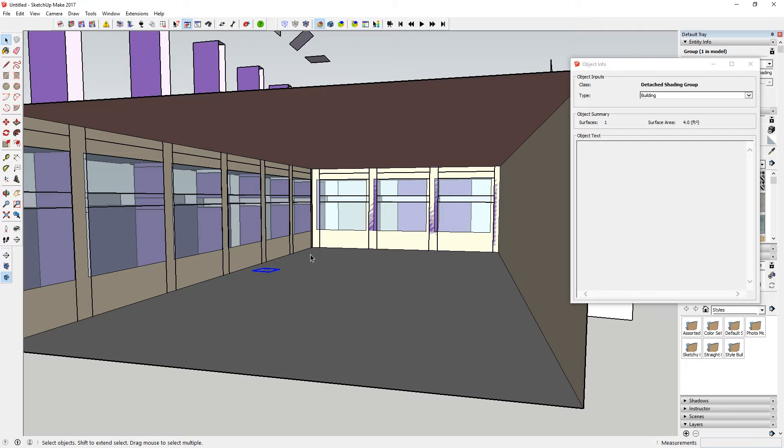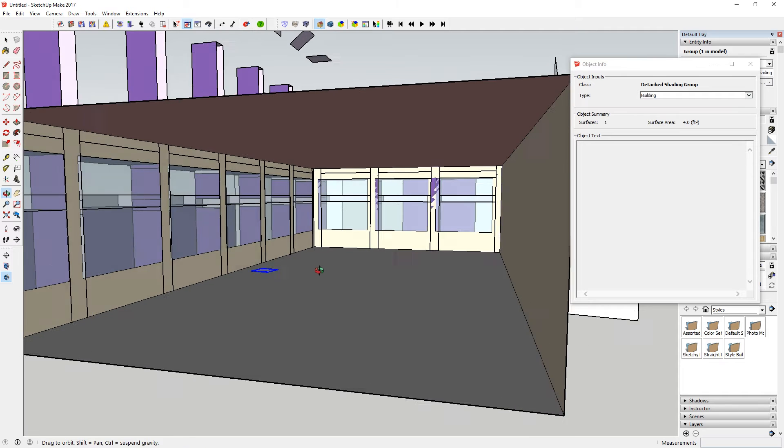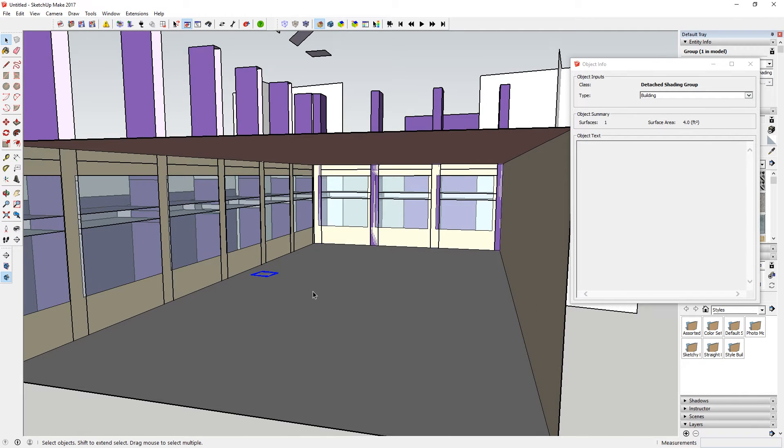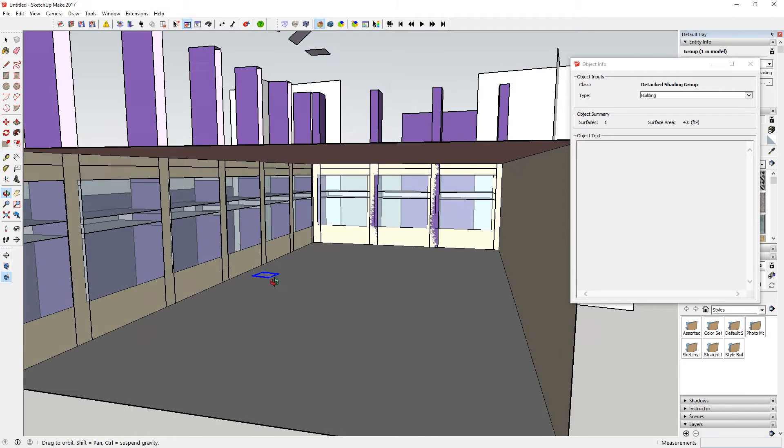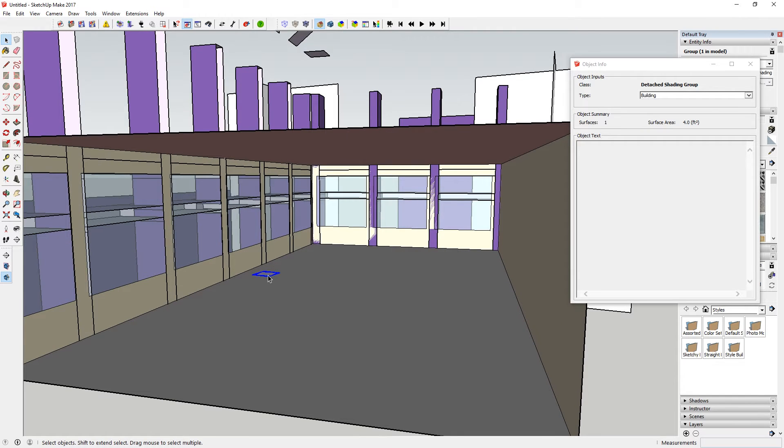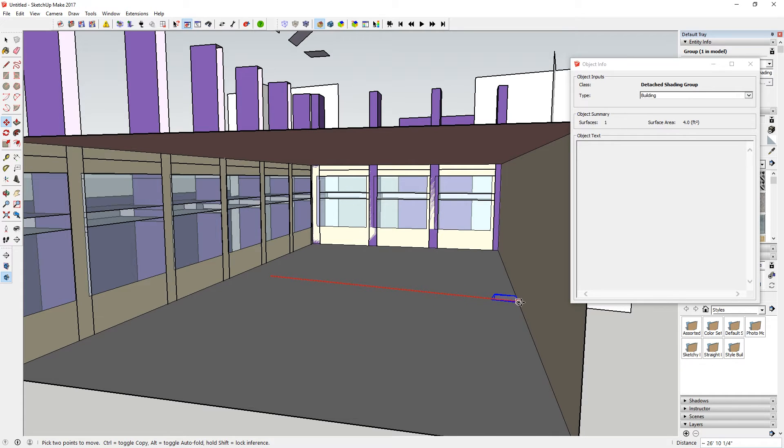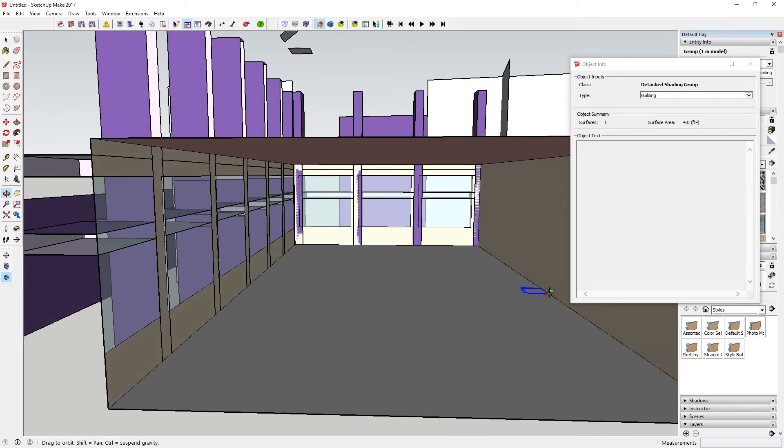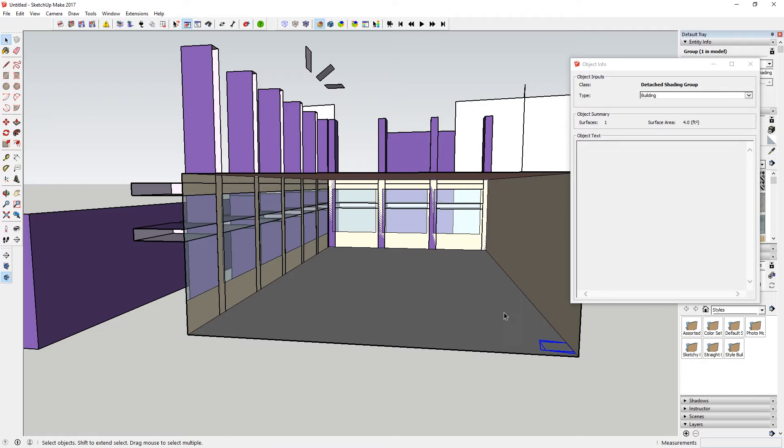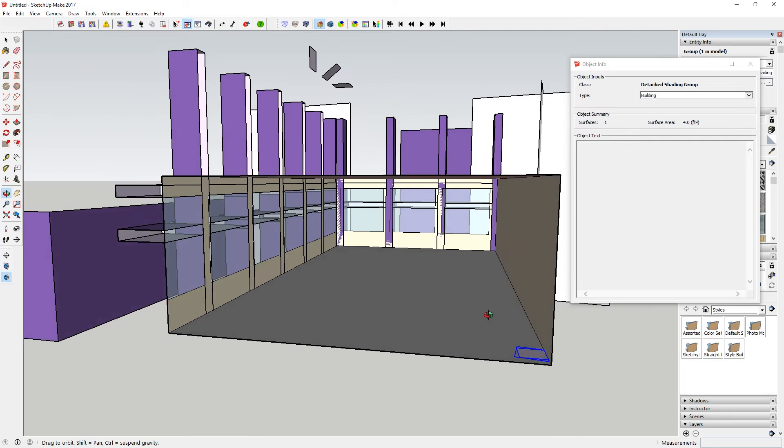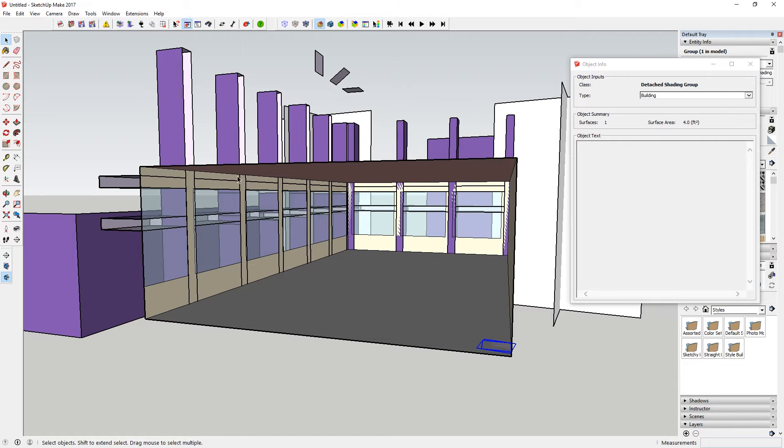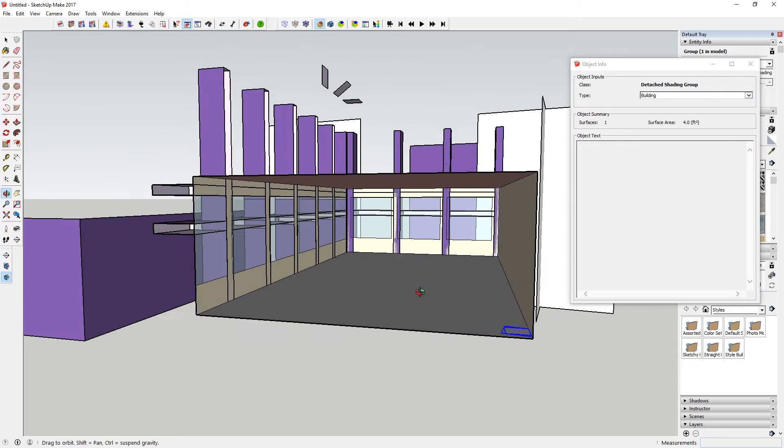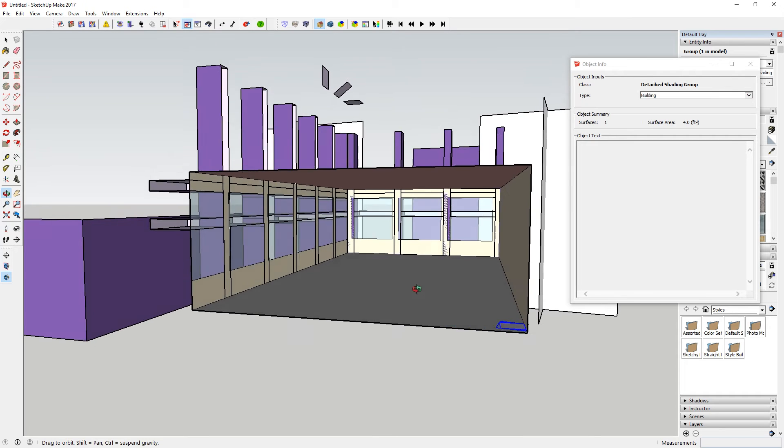So in order to accurately model the effects of daylight dimming in this zone, I'm going to position this sensor in the darkest portion of the zone that I feel would still get daylight. So I can actually back it up all the way over to here and move it maybe even to this corner and try to account for all of the dimming for the entire zone.